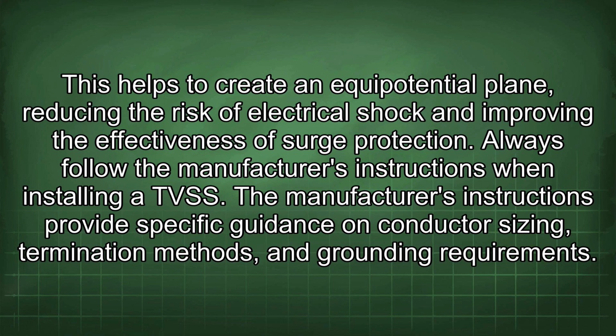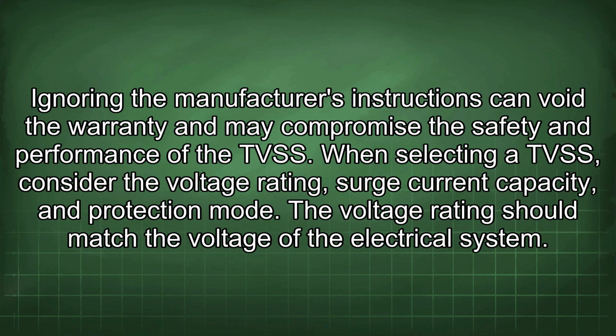Always follow the manufacturer's instructions when installing a TVSS. The manufacturer's instructions provide specific guidance on conductor sizing, termination methods, and grounding requirements. Ignoring the manufacturer's instructions can void the warranty and may compromise the safety and performance of the TVSS.